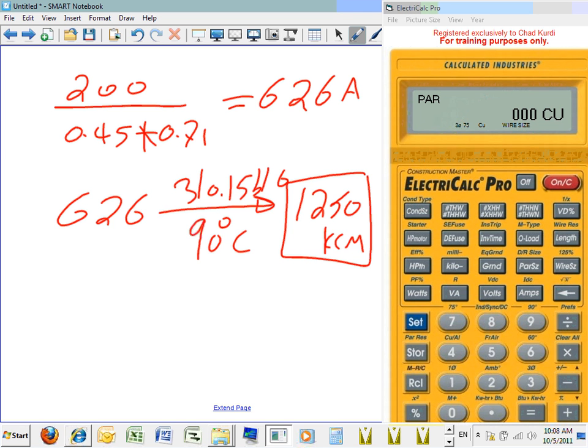But I can tell you, at this level, if we were doing branch circuits, I would. But if I'm doing a feeder that high, I wouldn't count it. Any question, guys? And the code says if it's carrying harmonic, so it's your judgment. Branch circuits are definitely carrying harmonic. Feeders will carry harmonic, but it will be mitigated by the non-harmonic loads, and there are IEEE studies showing these two together neutralize each other.